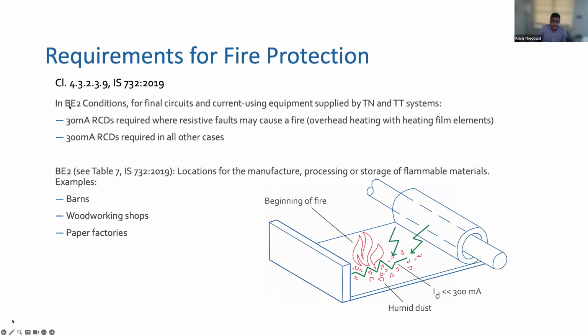Fire protection says, in BE2 conditions like Gerard showed us, for final circuits and current-using equipment, you need 300 milliamp. If there's a resistive fault, 30 milliamp for resistive fault, 300 for other cases.